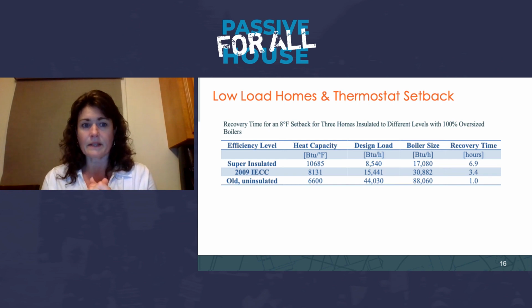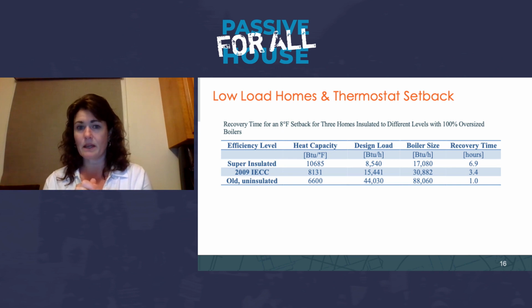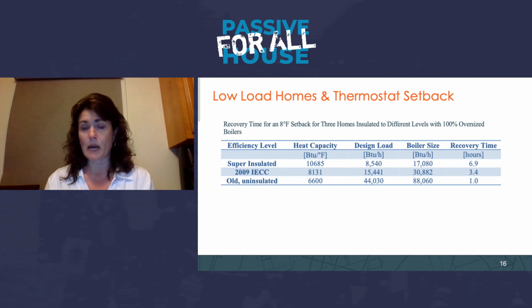This slide is showing a comparison, the same size home in the same location, on how big the heating system is, if we doubled the heating system for each of these design loads, how long it would take the house to recover from an 8-degree setback. Say they went away for 3 weeks on vacation, turned the heat back to 60, and come back wanting to bring it up to 68. If I had a super insulated home with a design load of only 8,500 BTUs per hour, and I doubled it, it would still take 7 hours for that house to recover. So I'm just trying to put all of this in perspective on how these things behave.